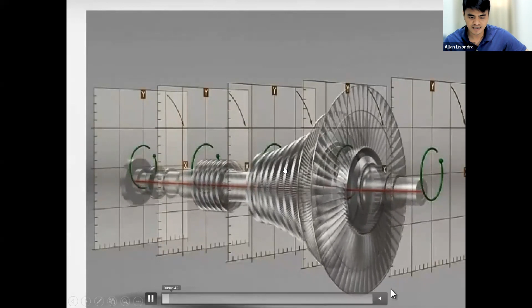Let's say this is your first rigid, now it is your second critical. As we know, in equipment like a rotor and generator, and even in turbines - HP, IP, LP - there are different critical speeds. As you can see, sometimes the critical speed here is low, here high, so there are some differences. Each part, when it reaches this critical speed, the vibration will amplify.